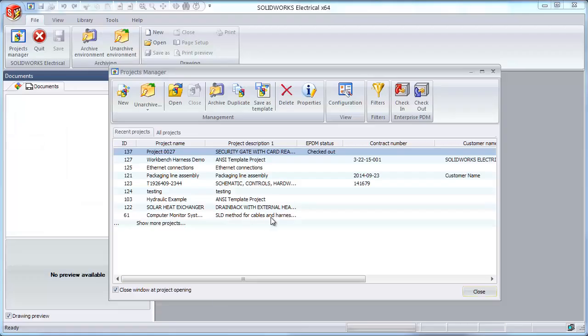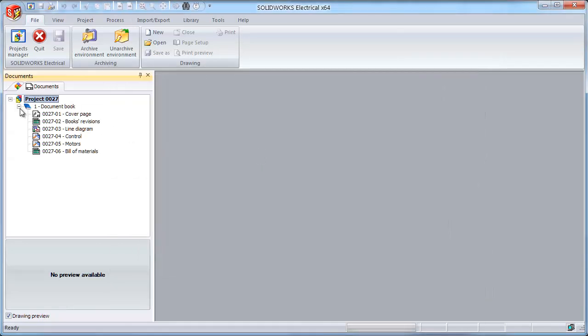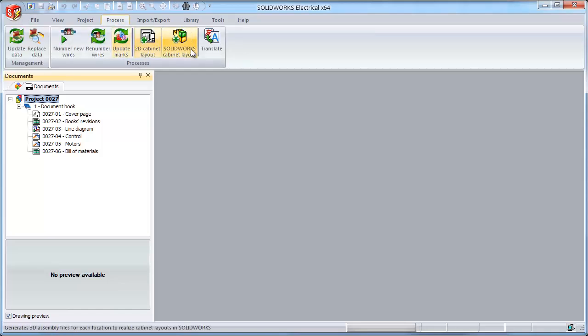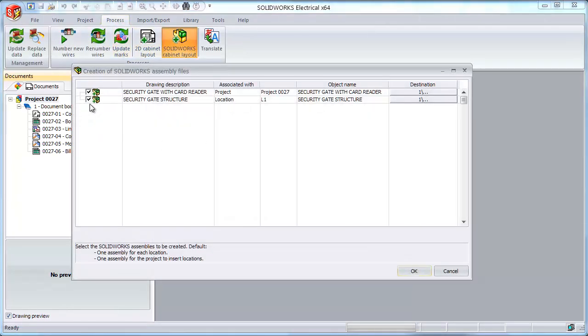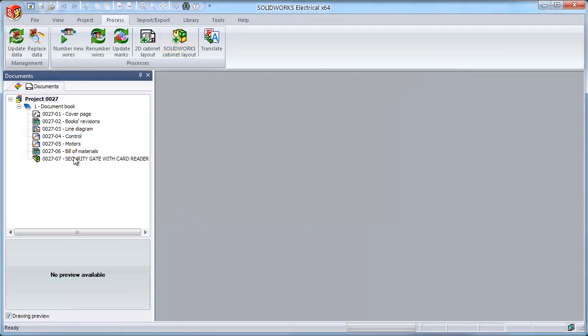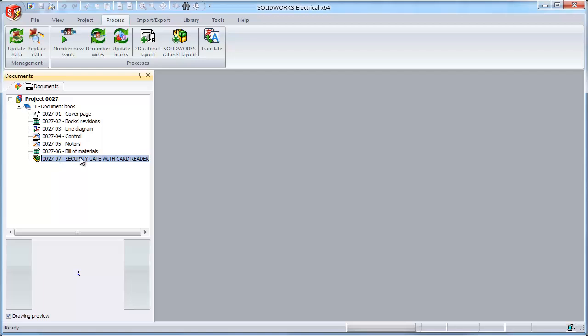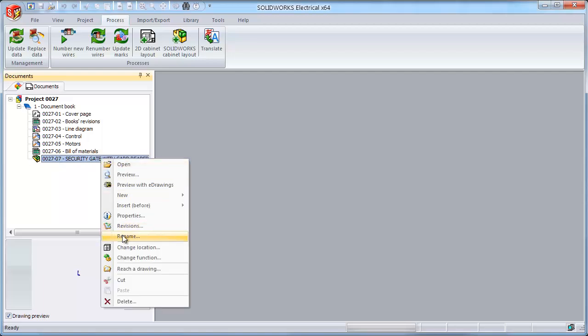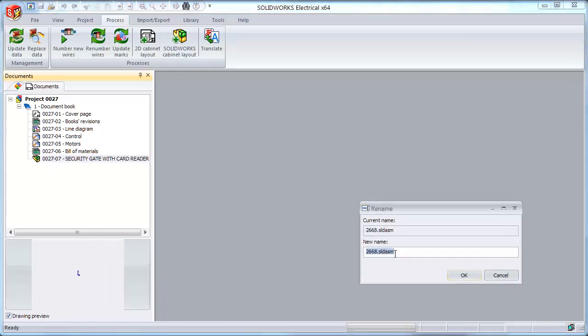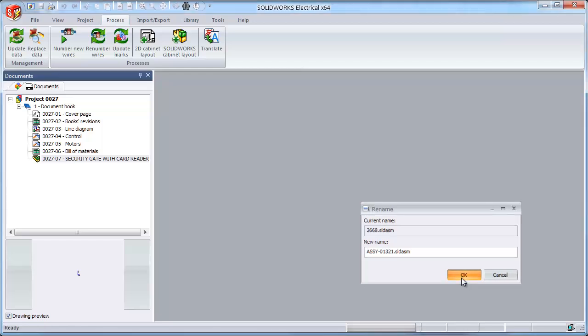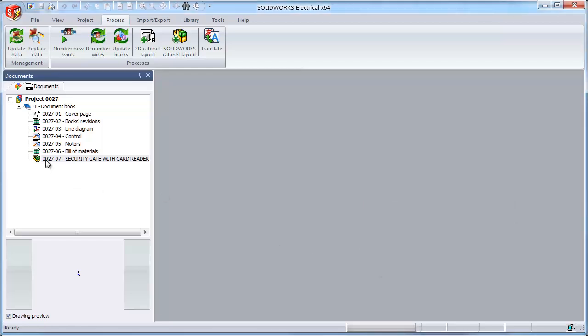Now we're also going to go ahead and copy that file name. Now back in SOLIDWORKS Electrical, now this can be done either on the schematic side or from SOLIDWORKS Electrical 3D. We're going to go into our Cabinet Layout tool and create a SOLIDWORKS assembly for the top-level electrical model. So we have our new electrical model created, and the key is to use the same name as the Enterprise PDM file. So we're going to simply rename the file and paste in the Enterprise PDM-generated serial number. So now when the project is checked in, this assembly will also be checked in and tied to the assembly that's already linked into ePDM.